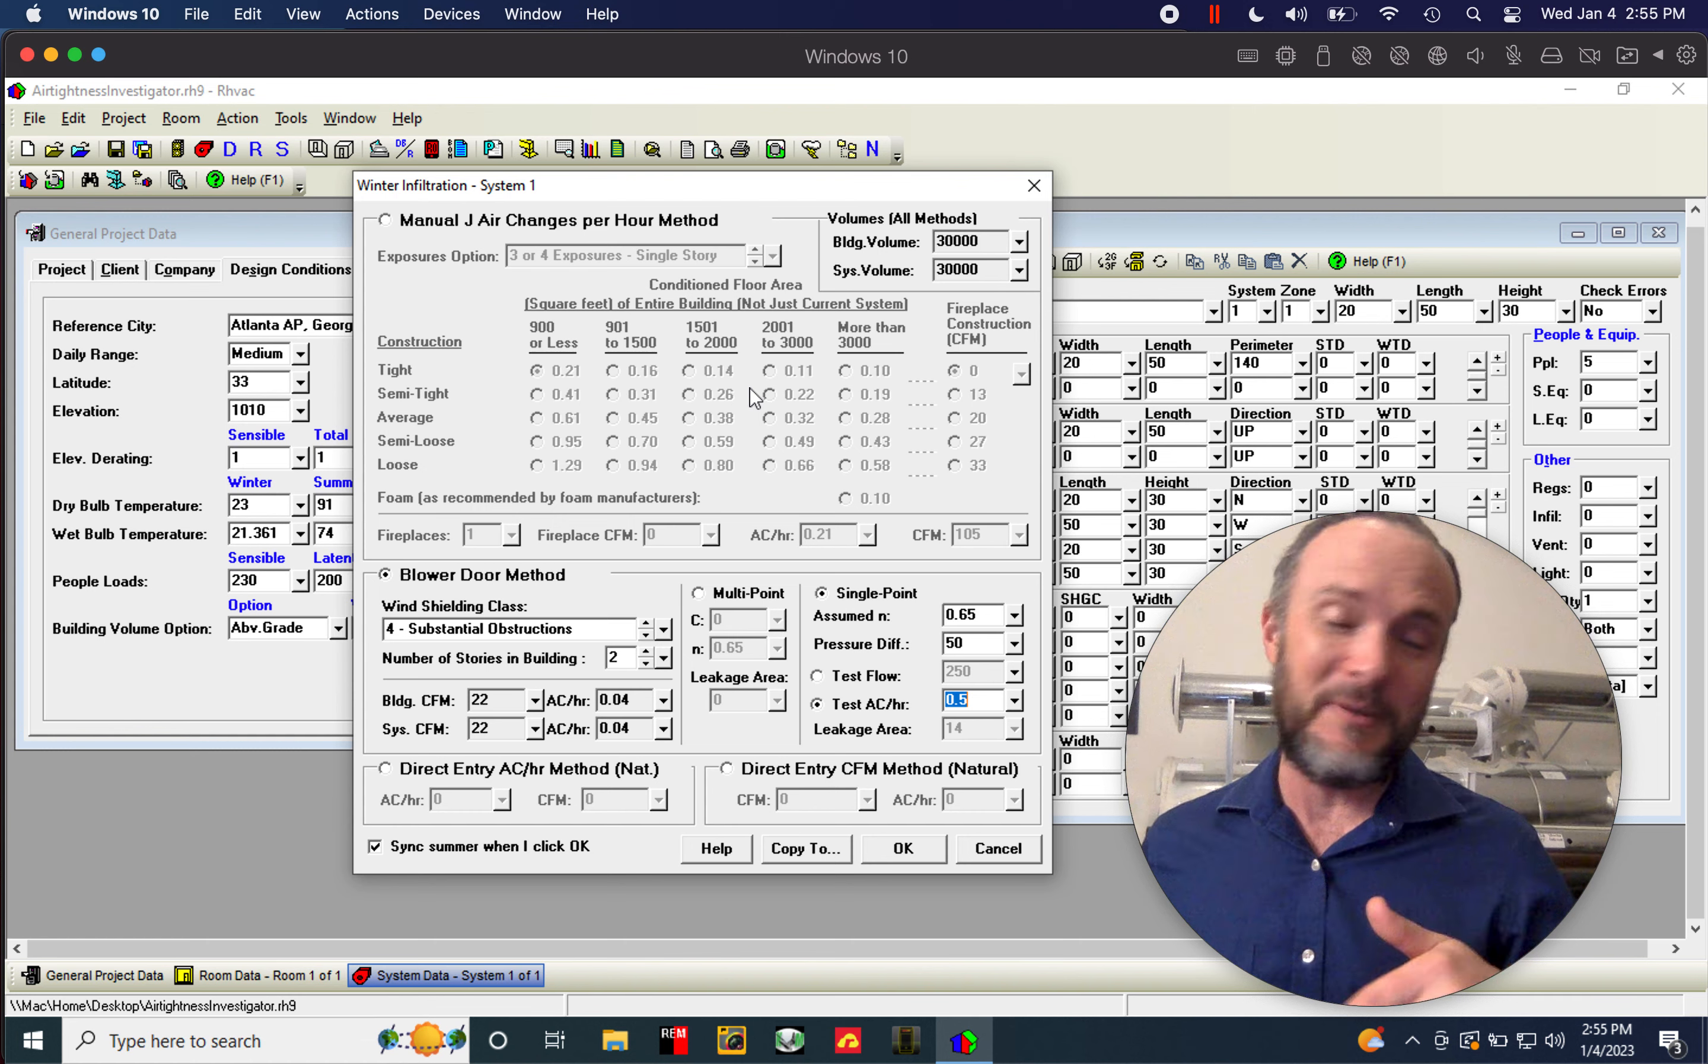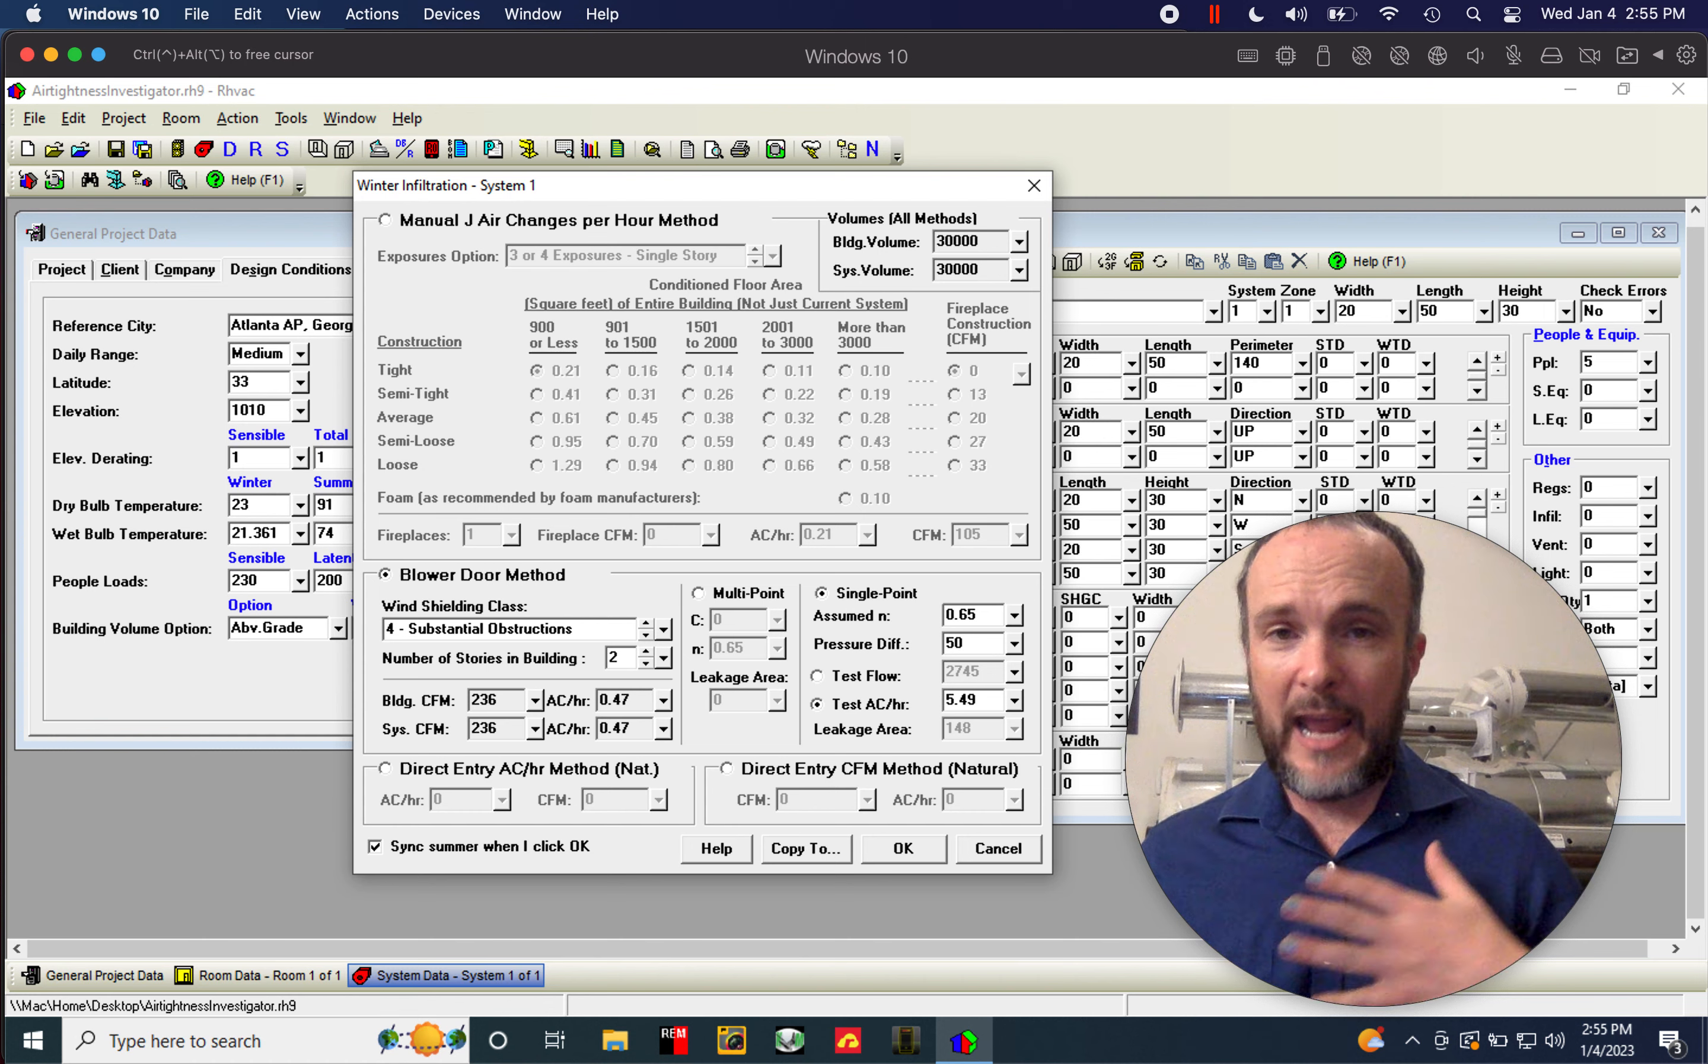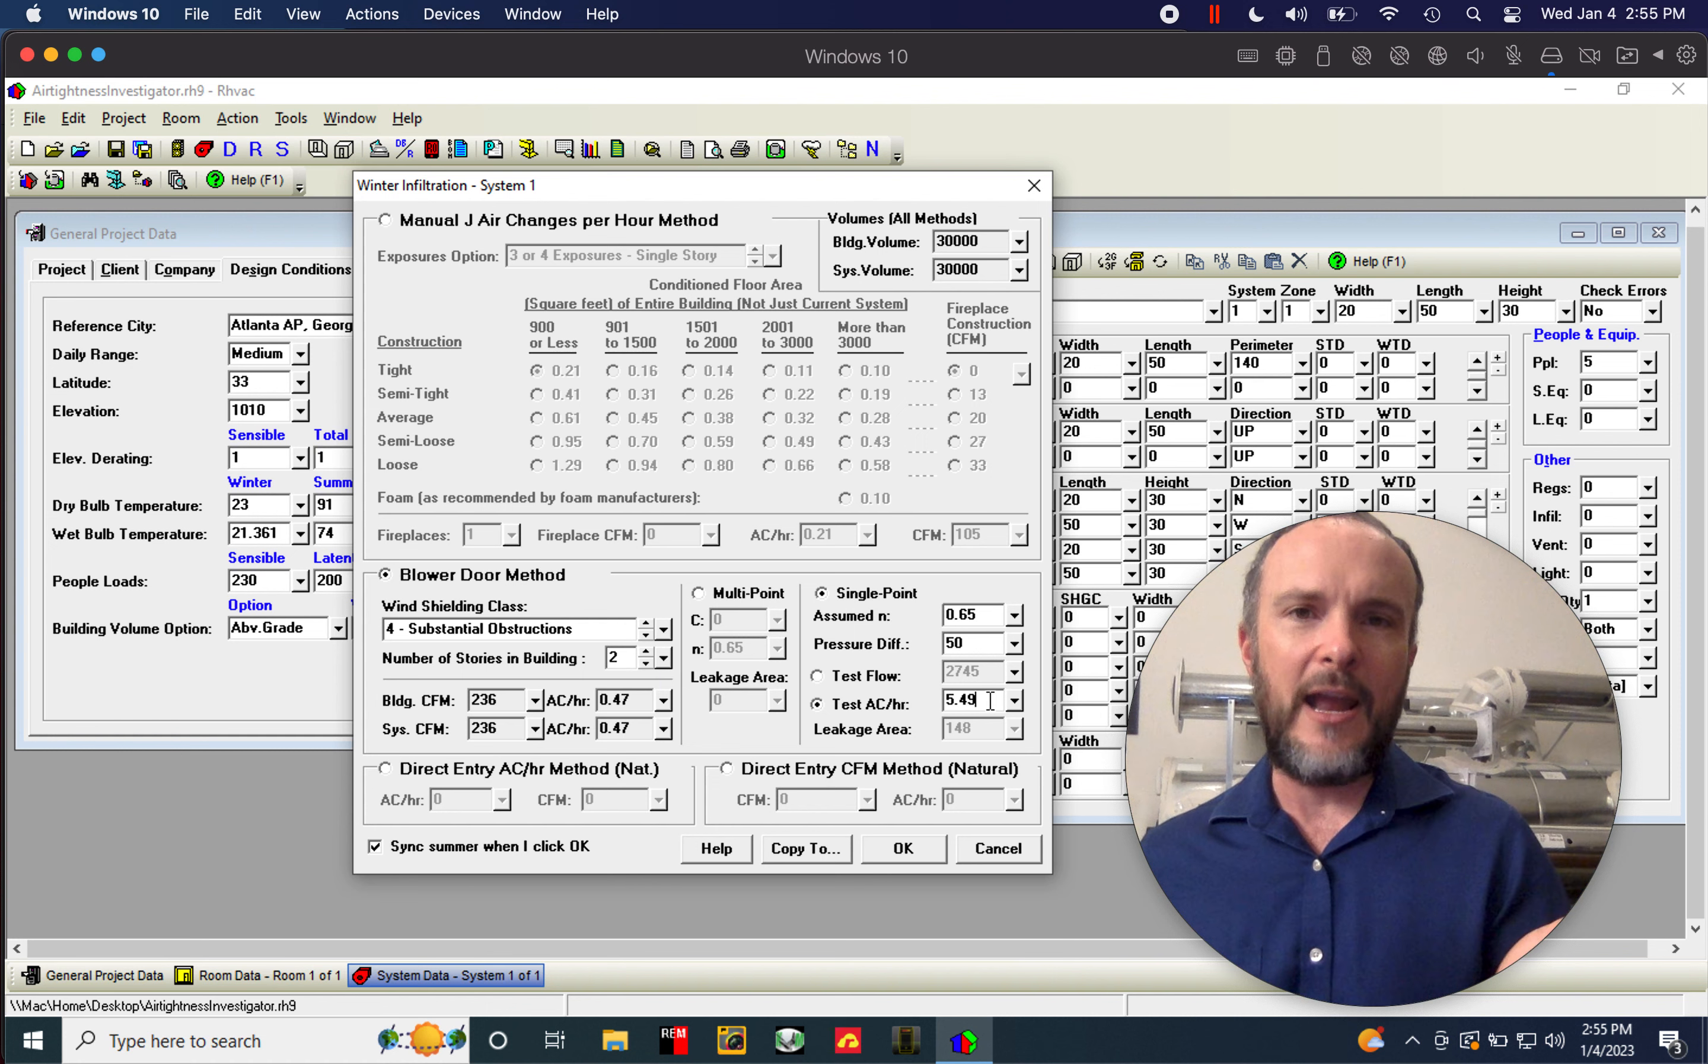They might not be because the municipality might not be enforcing this, which doesn't change the fact that it's still a state law and there still could be sued by the buyer. That's all beside the point. What you really need to drive out is if you're going to put five in here, what I might do, if you're trying to play it safe and remember that there is fluff, there's fat built into manual J already, but if you wanted to, you could put 5.49 because that is still five. And I know that because I teach people to use blower doors for code testing and the code says nice round number. It does not say 5.0. So they might be passing code at 5.49. And if you assume that it's just five, then they're getting an extra 10% air leakage that you didn't build into your calculation. So there's that.